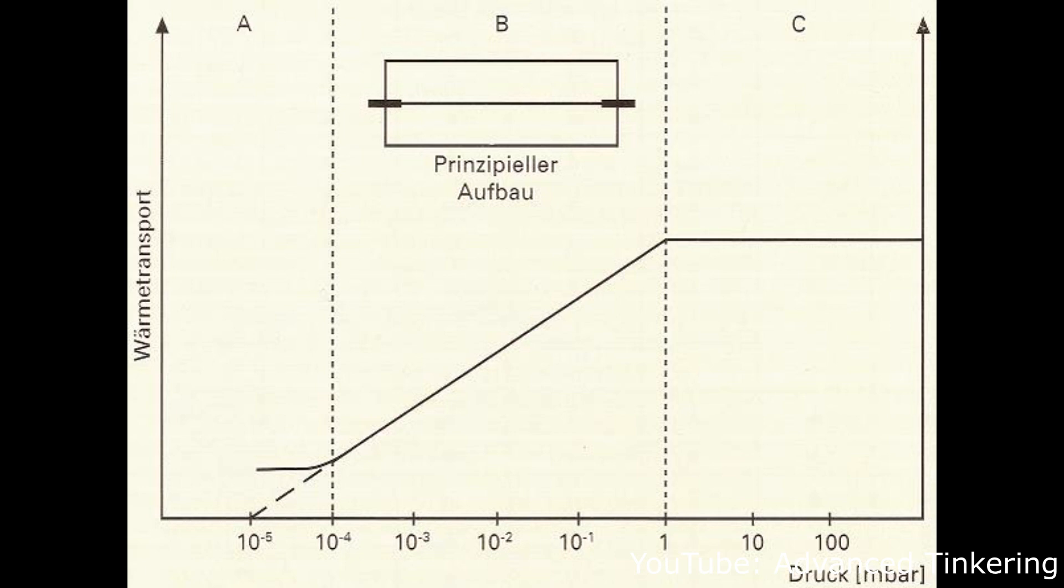The Pirani gauge is only capable of measuring a pressure reliably in a range of about 10 to the power of minus four to one millibar, and the capacitance gauge is able to measure the pressure from one millibar upwards, so one millibar to around room pressure, so a thousand millibars.